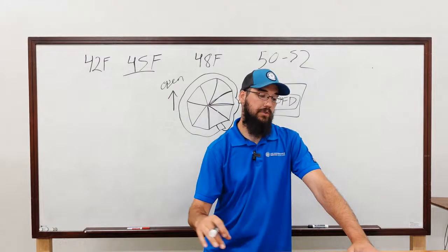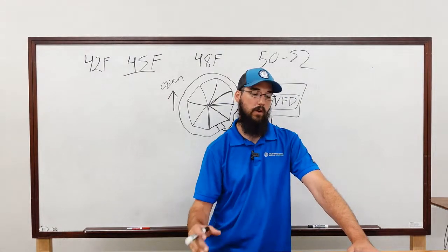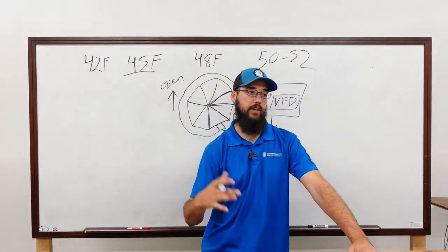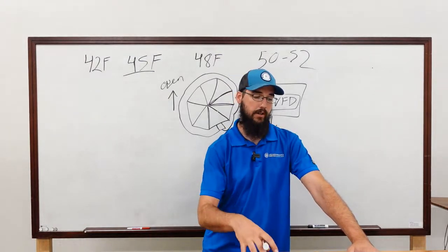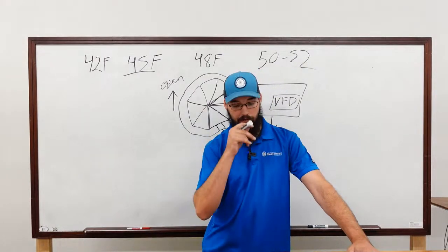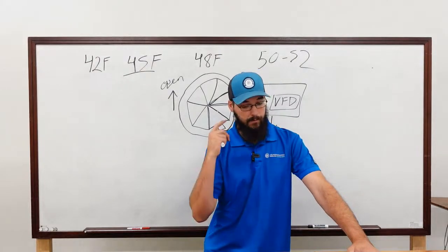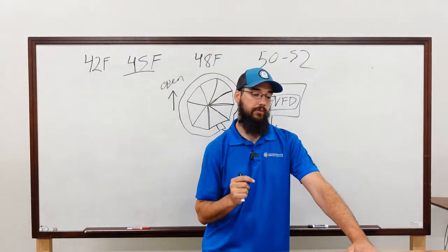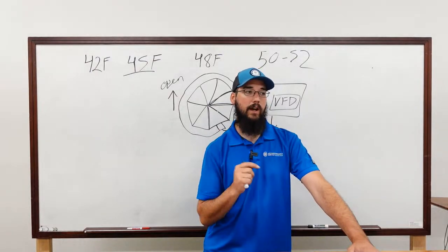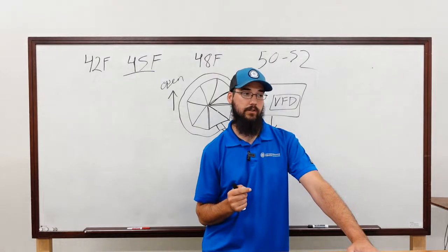But the most common in our area, at least, would be more of a Y delta start. So we see on the older machines before VFDs really started to take over the market, Y delta was a very common choice. Now, something that I'm going to throw out here that I didn't realize for a long time, I misunderstood. There is a difference in Y delta motors and Y delta power feed, and it's two different terminologies.